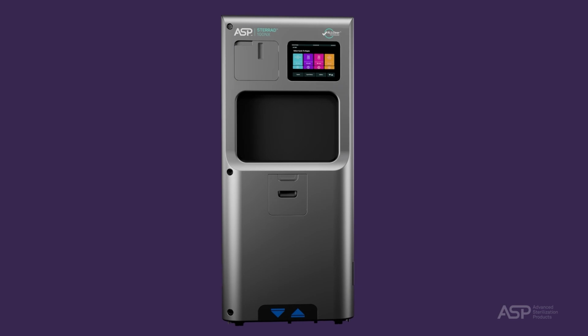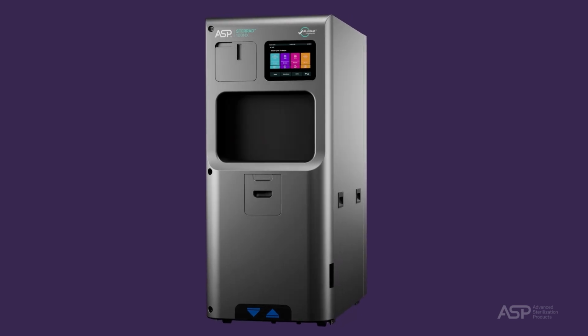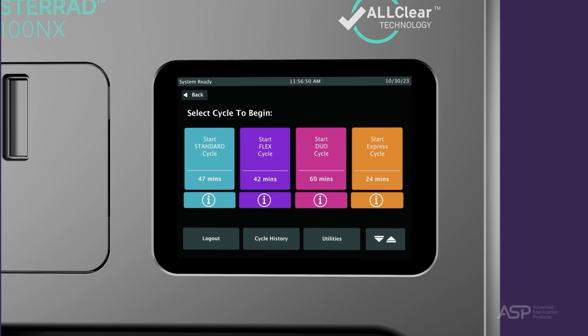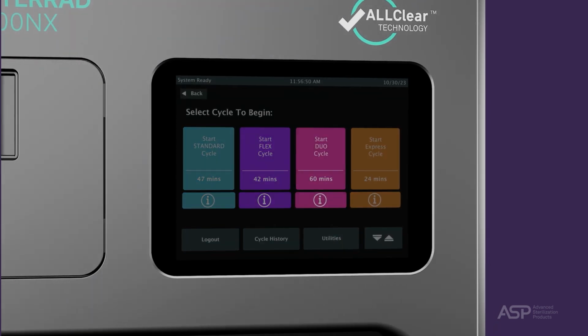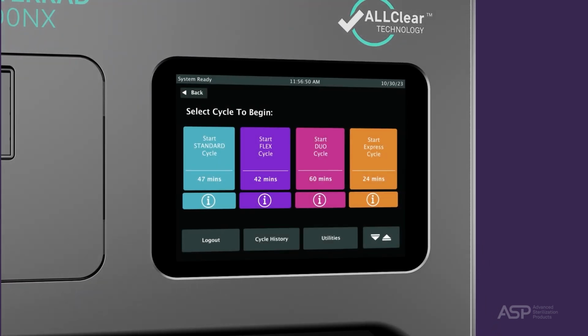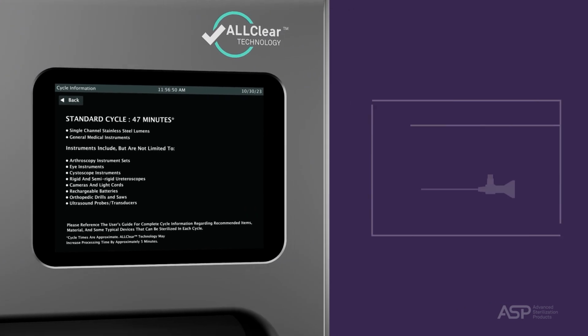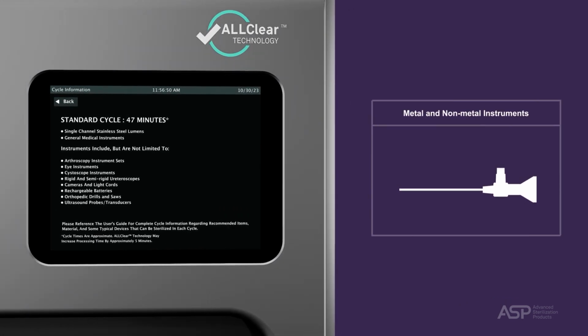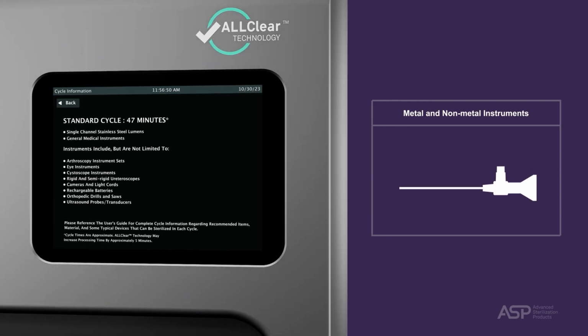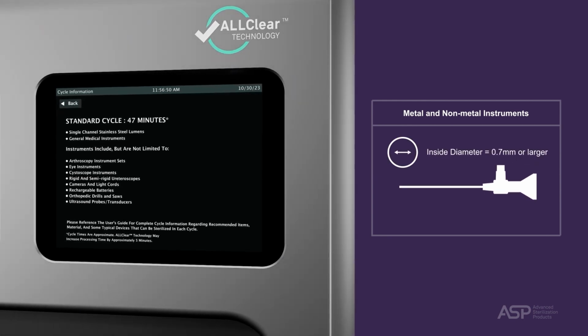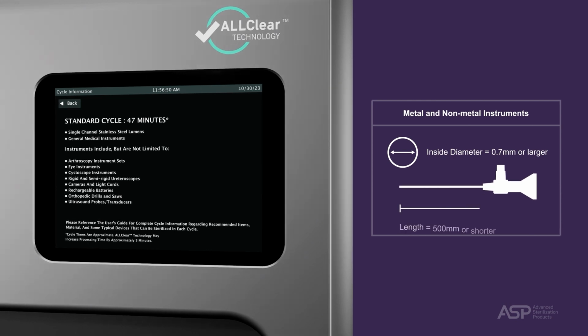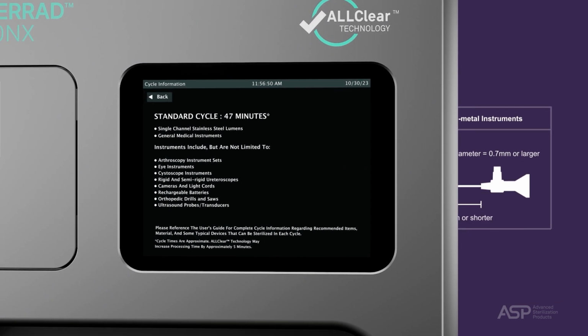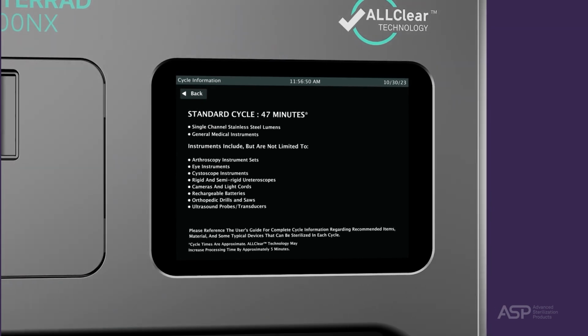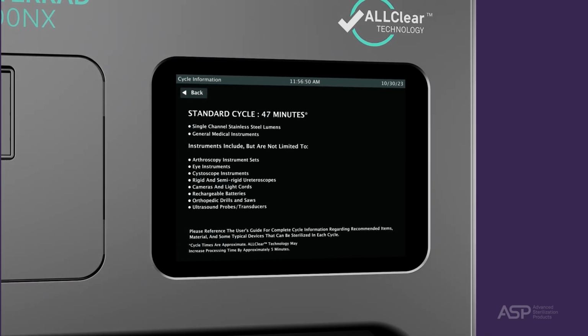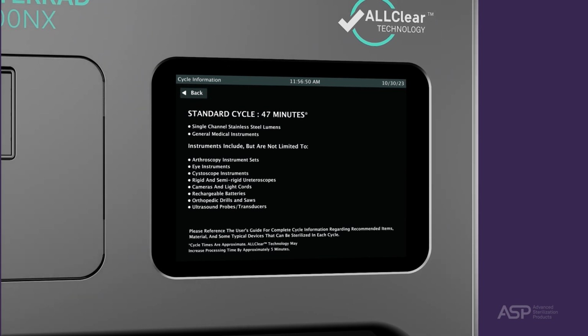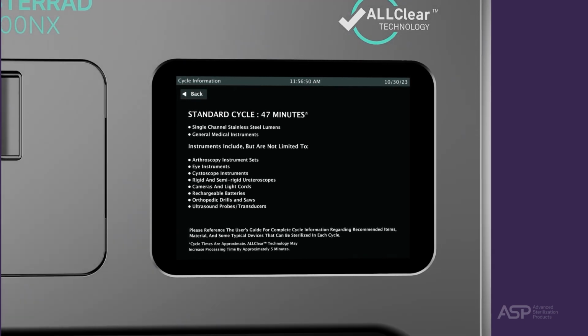Let's review the available cycles and what can be reprocessed in the STERRAD 100NX sterilizer with ALLClear technology. The available cycles are standard, flex, duo, and express. The standard cycle is 47 minutes and should be selected for general metal and non-metal medical instruments, including hinge devices, and single-channel stainless steel lumens with an internal diameter of 0.7 millimeters or larger and a length of 500 millimeters or shorter. Typical devices would include arthroscopy and laparoscopic instrument sets, eye instruments, cameras and light cords, rechargeable batteries, orthopedic drills and saws, and ultrasound probes.